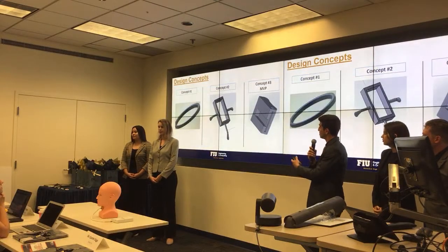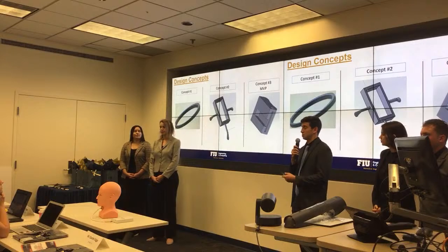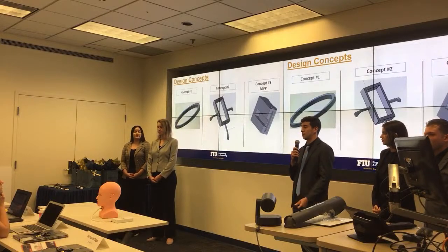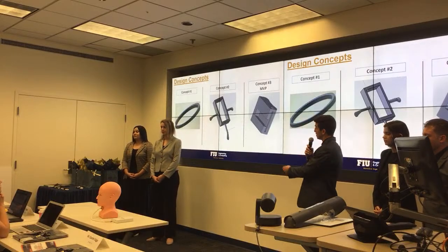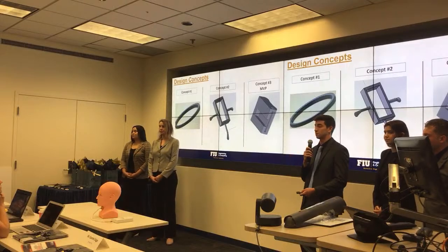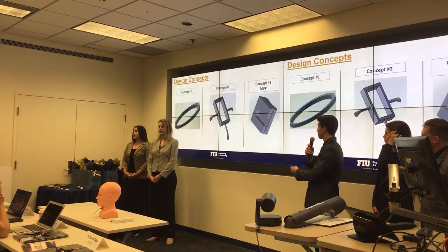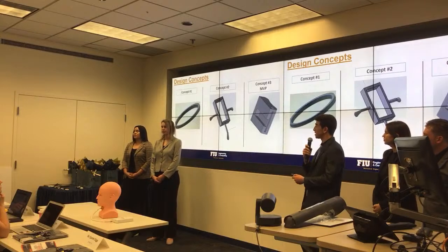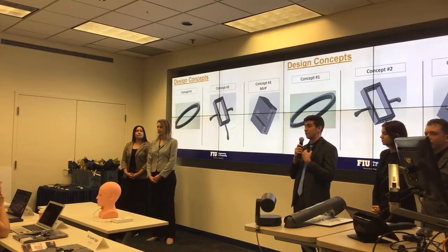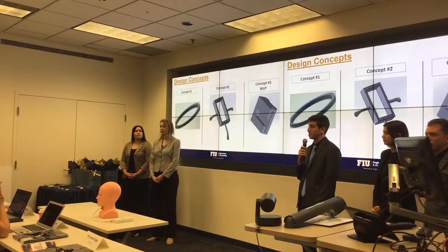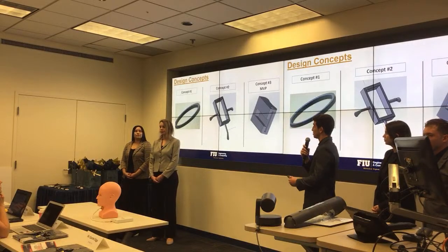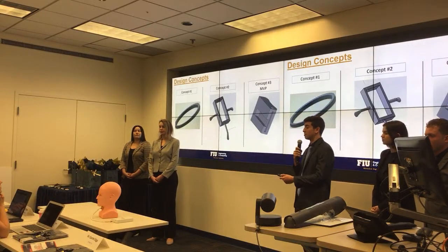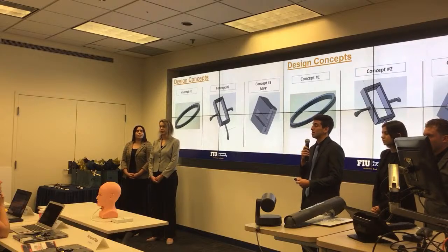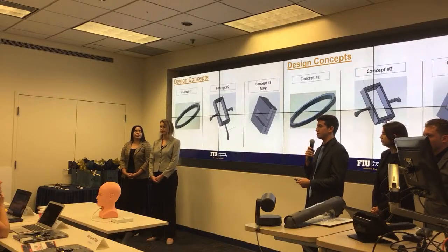So these are some of the design concepts that we came up with. The first one is like a necklace to be worn around the patient's neck, where the accelerometer is inserted into that small chip there in order to record the signal. In the second one, the 3 rods would be taped to the patient's neck, and the accelerometer would go into that slot, having direct skin contact with the patient. These 2 were not chosen simply because our accelerometer is very high sensitivity, so it would cause a lot of noise to be added to our signal.